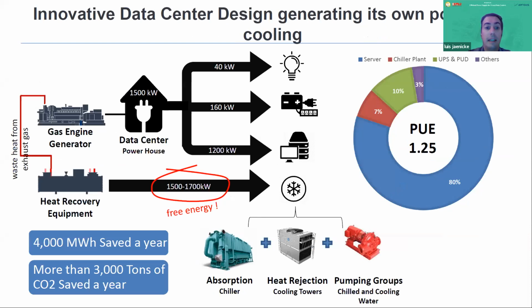Okay, so if we change the design with a cogen power and cooling production at site, then I'm not changing anything related with the servers or the ITs. Still, I'm having 1.2 megawatt of IT load. My auxiliaries, UPS, lighting, etc., will remain the same. So 1.4 megawatts are still going for the same data center. What I'm essentially changing is where do I get the power? In this case, from a gas engine generator, it could be gas turbine, or it could be a fuel cell. But in this example, I'm using a gas engine, and essentially I'm replacing the chiller plant by using an absorption chiller plant.